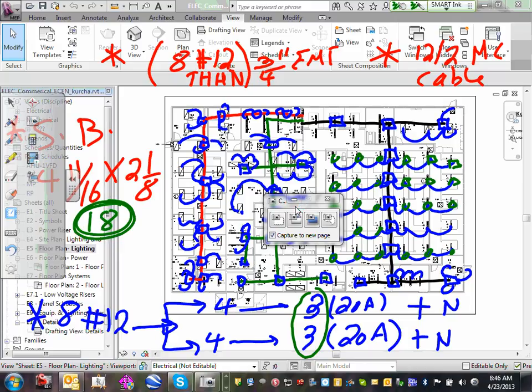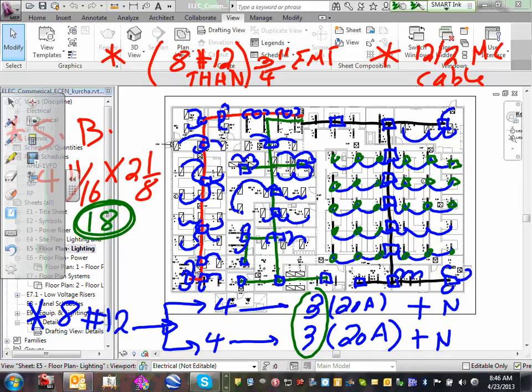I've done this exercise many times, guys. If you load this conduit up to 16 carrying conductors, if you go to the code and derate, you have to derate the THHN 30 amps, cut it by half, give you 15. By code, you cannot load a lighting circuit more than 16 amps. So how many amps did you lose? Only one. And if you look at your lighting circuits, you were using LEDs. That's the least voltage drop with number 12. And the building is small too. So under these circumstances, it wouldn't be a big deal.